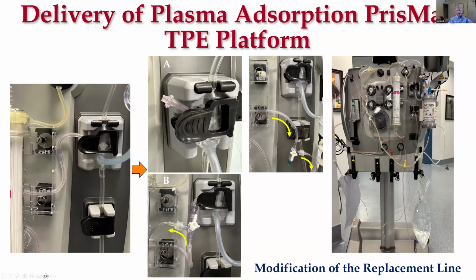to pump fluid out of this bag to match the amount of weight or fluid that would come into this bag. Technically, that would come into this bag. And I guess it works the other way, that it pumps fluid out of this bag into this bag, and so the amount that's removed here shows up here, and then the machine is happy. The other way you can do this, if you wanted to do the plasma exchange and the plasma adsorption, you hadn't programmed that at the beginning, you could aseptically put a stopcock in here, and this is where I would recommend. If you're in the middle of the treatment, then I think you're obligated to just heat seal this line.